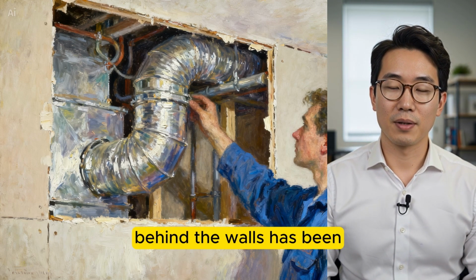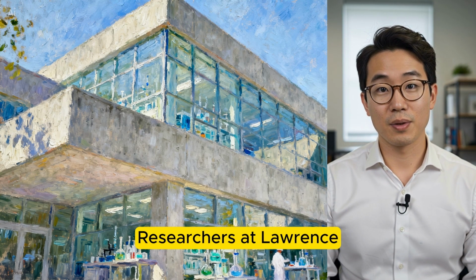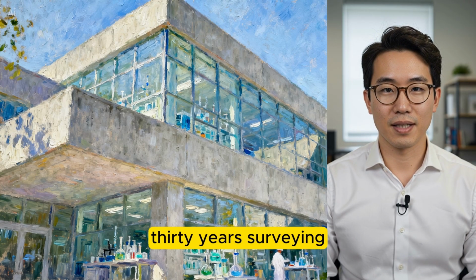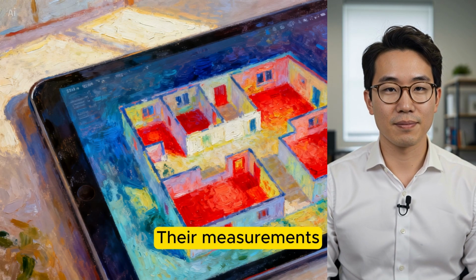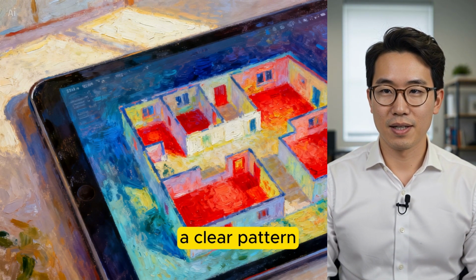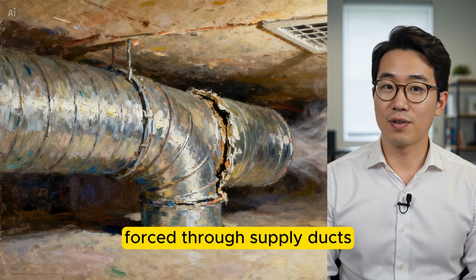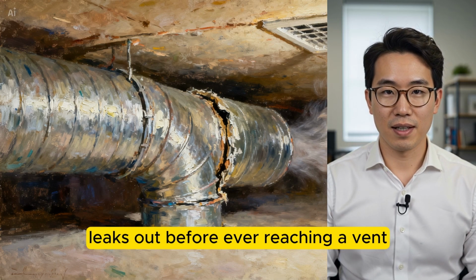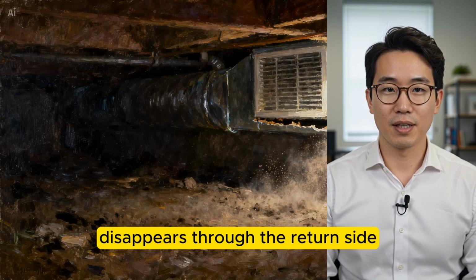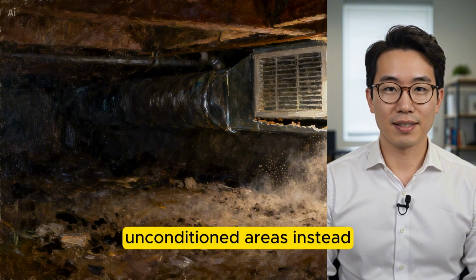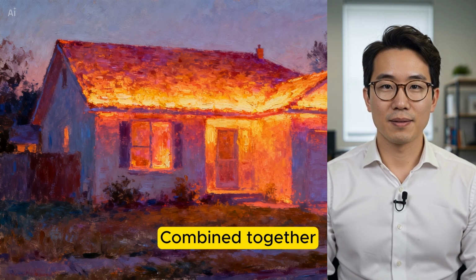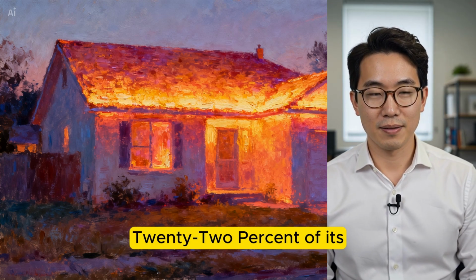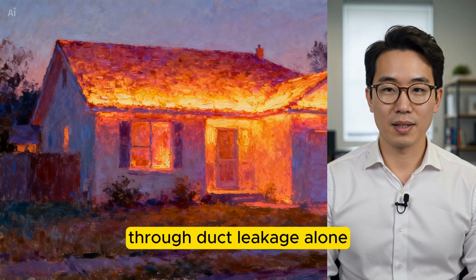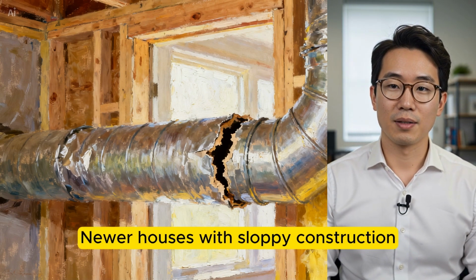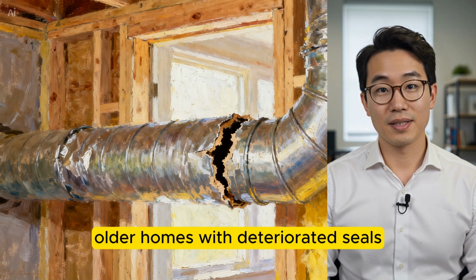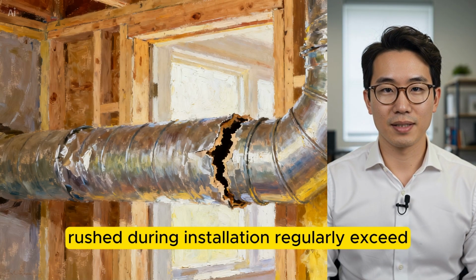What is happening behind the walls has been studied for decades. Researchers at Lawrence Berkeley National Laboratory spent more than 30 years surveying residential duct systems. Their measurements across thousands of homes revealed a clear pattern. Around 10% of the air forced through supply ducts leaks out before ever reaching a vent. Another 12% disappears through the return side, pulling air from unconditioned areas instead of the living space. Combined together, the average American home loses 22% of its heated or cooled air through duct leakage alone, and that is only the average.